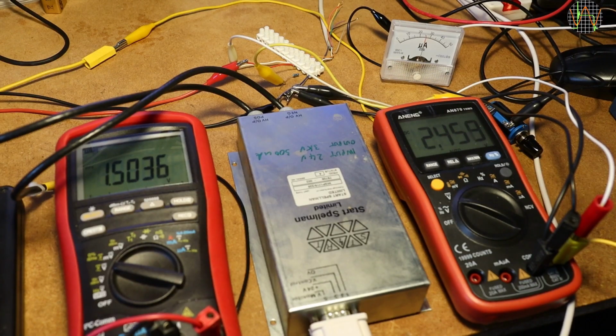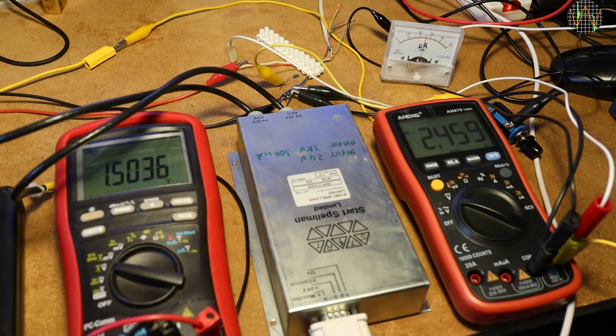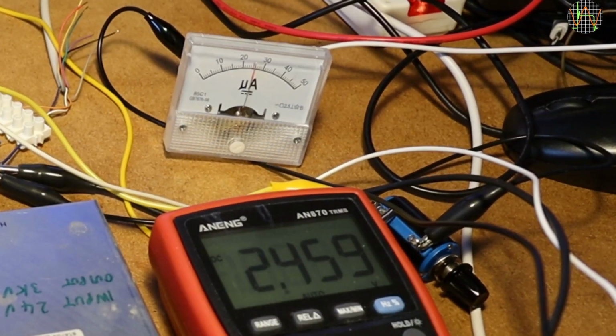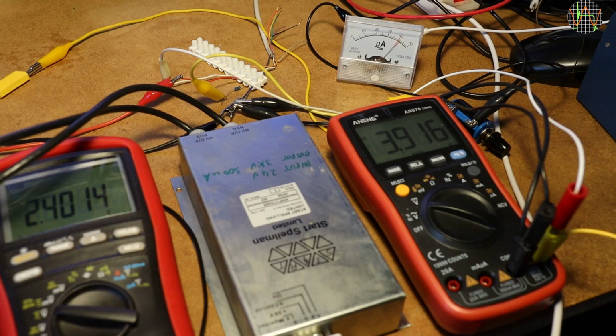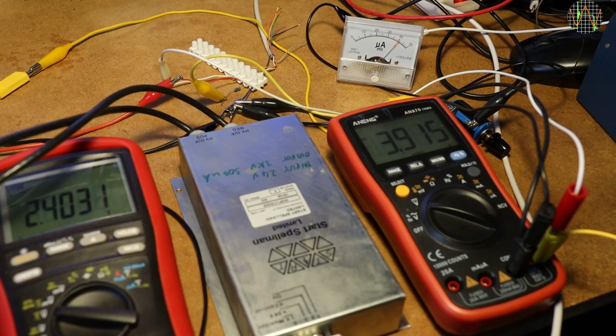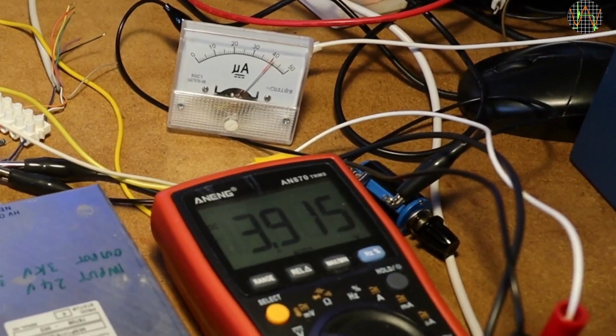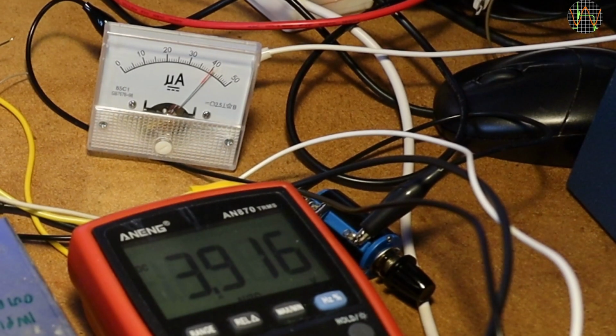At 1500 volts, which is half of the max voltage, the pointer of the analog meter showing the monitor voltage should be right in the middle of its scale, which it is. At 2400 volts, which is 4/5 of the max voltage, the meter should be on the 4 of its 1 to 5 scale, and it does. So this solution would work, but of course I don't really want to see a 4 on the meter, but 2.4 kilovolts. So I decided to park the solution for now and look at a digital alternative in form of the now ubiquitous panel meters.